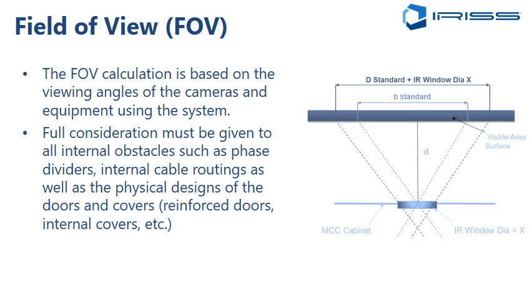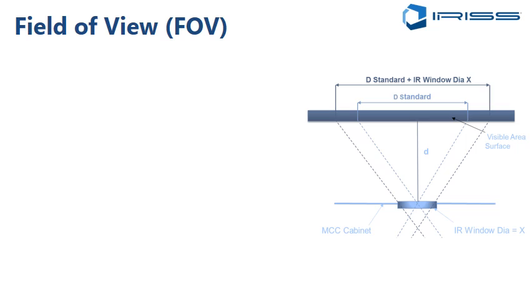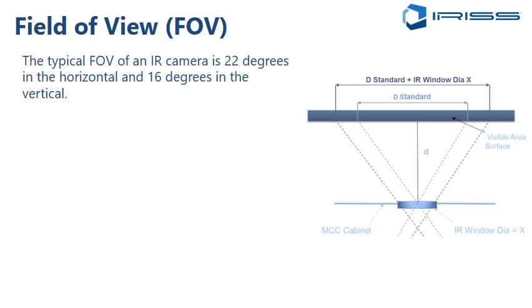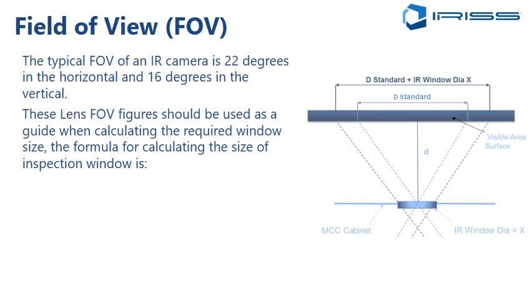So when you're looking at field of view, there's going to be some mechanical obstacles, but the calculations are based on the lenses of the systems that you're using to look through the window itself. As I said, the field of view is limited by the actual camera lens itself. Typical field of view of an infrared camera is 22 degrees in the horizontal and 16 degrees in the vertical. Now these figures are just a guide, and I'm going to go through some basic calculations to work out the size of an inspection window.